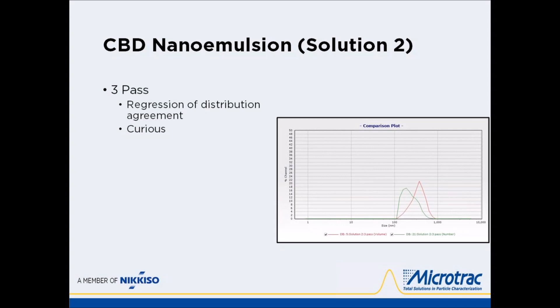However, when we jump to the 5 passes, again, near perfect agreement when it comes to the volume and the number distribution, and that tells you that it's a really, really tight distribution of particle sizes. The number distribution tells you it's around 260, whereas the volume distribution tells you it's around 316.